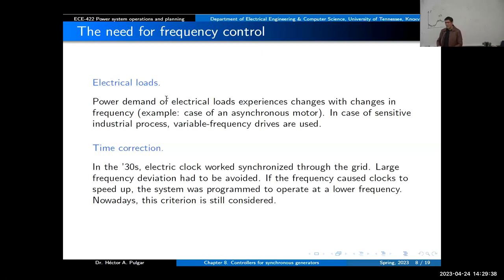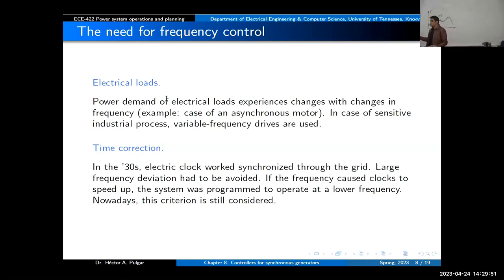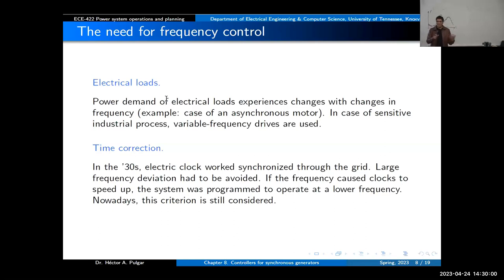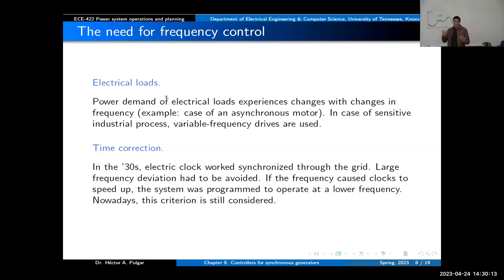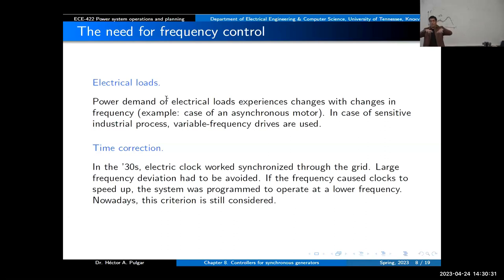In the 1930s, most clocks were electric and synchronized through the grid. If the grid operated at very low frequency, all the clocks would run behind, and people might show up late to work. The operator would then speed up the machine and have a frequency higher than nominal just to catch up with time. The funny thing is operators still use this today. Over time, when the frequency has been below nominal for a while, you will operate all machines at a frequency above nominal so that the time error is minimized over time.